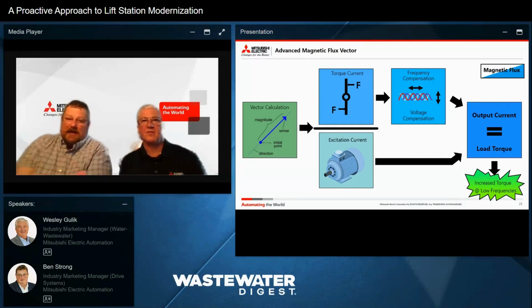Here's basically an outline of the difference. I didn't really outline volts per hertz. Typically, if you take the drive out of the box, it defaults to volts per hertz. So for this frequency, we output this voltage and we don't have any feedback. So we don't really understand how much current the motor's using. We don't understand if the motor's even spinning in volts per hertz mode.